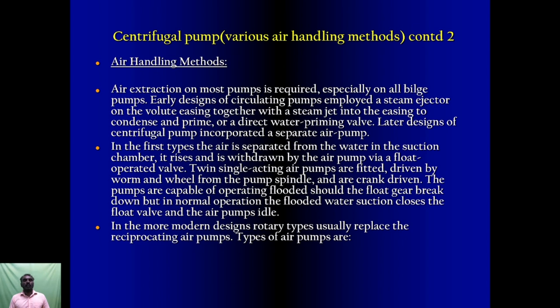It rises and is withdrawn by the air pump via a float. Twin single-acting air pumps are fitted, driven by worm and wheel from the pump spindle, or crank driven. The pumps are capable of operating flooded should the float gear break down, but in normal operation, the flooded water suction closes the valve and the air pumps idle. In the more modern designs, rotary types usually replace the reciprocating air pumps.